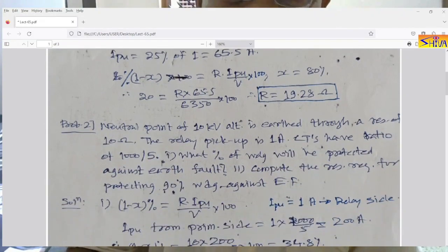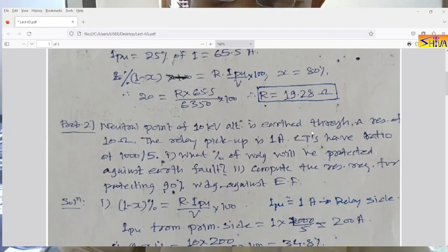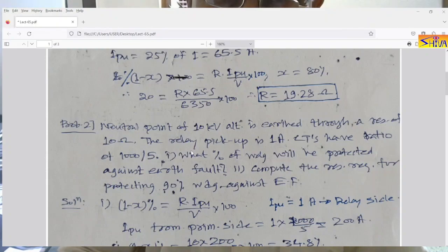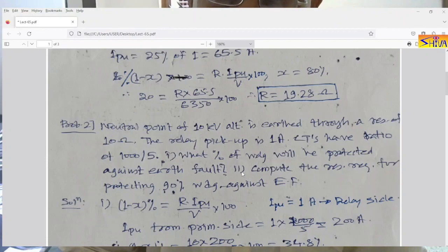Second numerical: the neutral point of a 10 kV alternator is earthed through a resistance of 10 ohms. The relay pickup is 1 ampere — and since it is only 1 ampere, this is from the relay side. The CT has a ratio of 1000/5, so we use this to find the primary-side current. Part one: what percentage of the winding will be protected against earth fault? Part two: compute the resistance required for protecting 90% of the winding against earth fault.